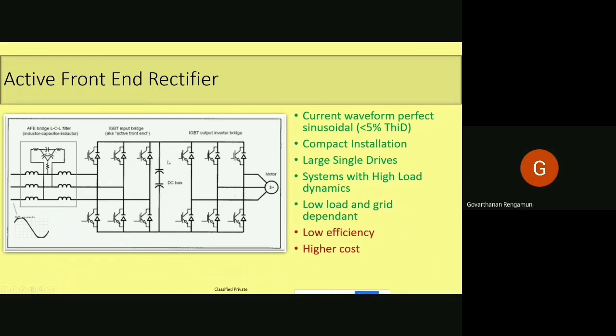Here you can see the IGBTs can switch from AC to DC section and DC to AC section also. So the main advantage of this with respect to variable frequency drives is that if there is regenerated energy from the motor, that can be supplied to the grid, because this will be acting like a bidirectional converter. Additionally, these IGBTs will be switching in a fashion to reconstruct the distorted waveform into a sinusoidal one. Here it will be acting in a boost mode.